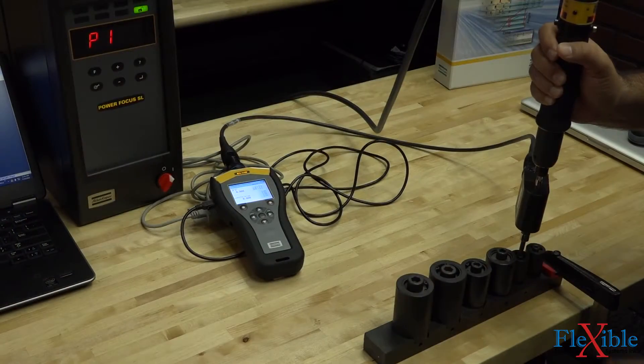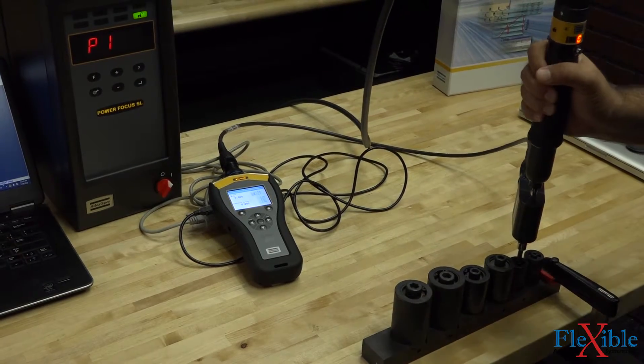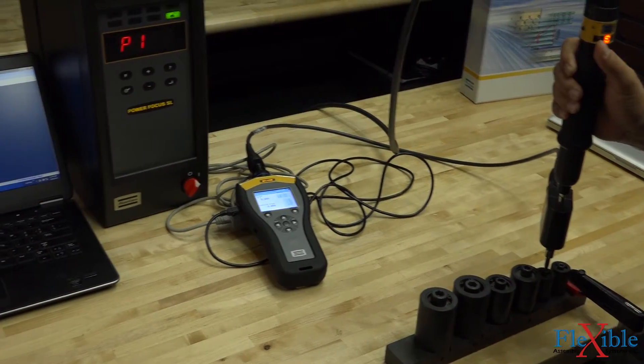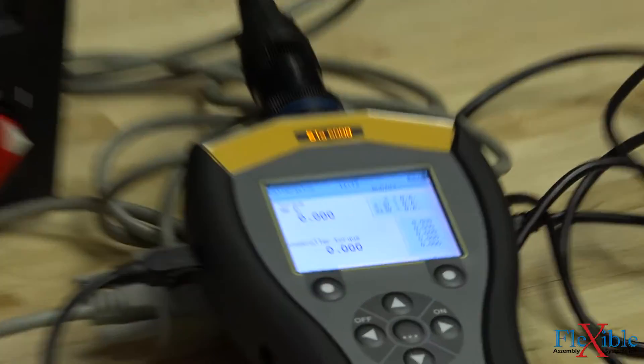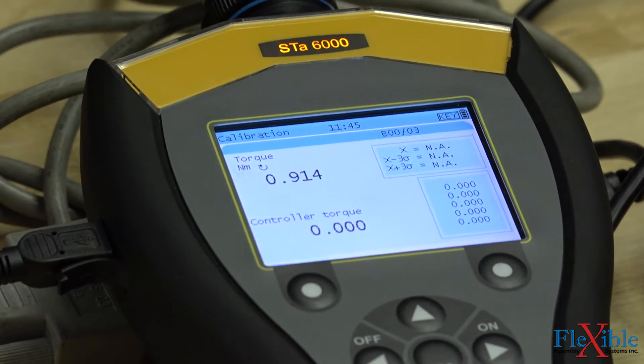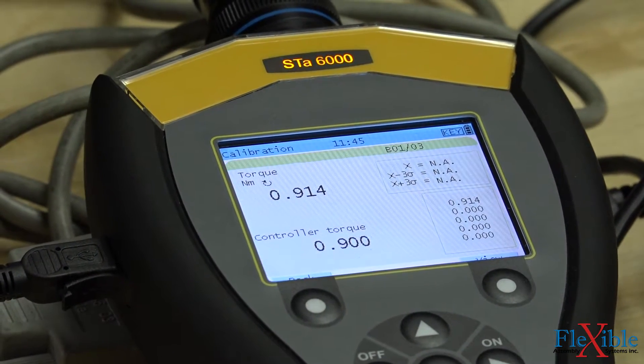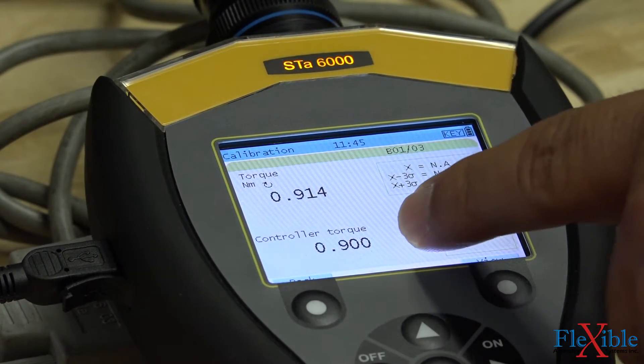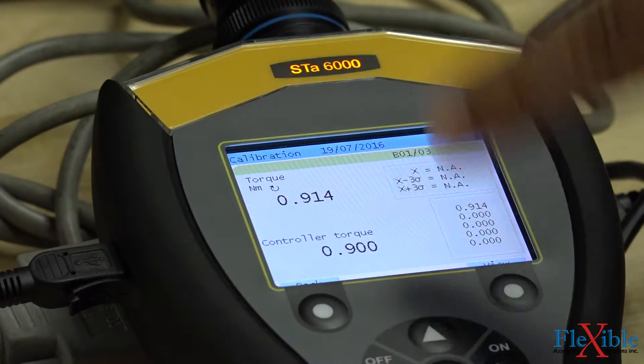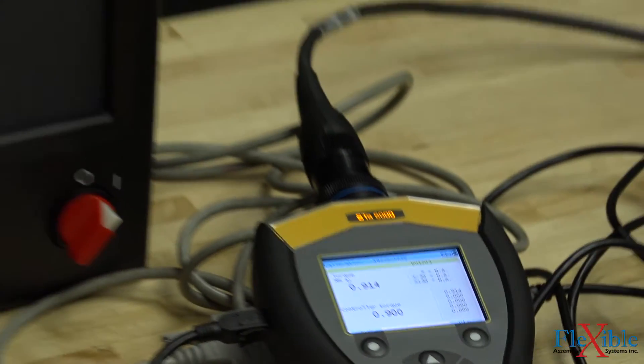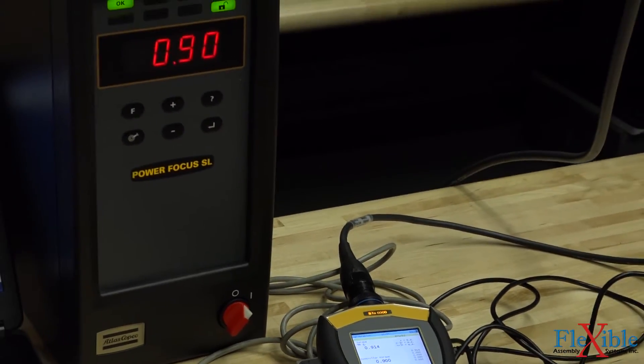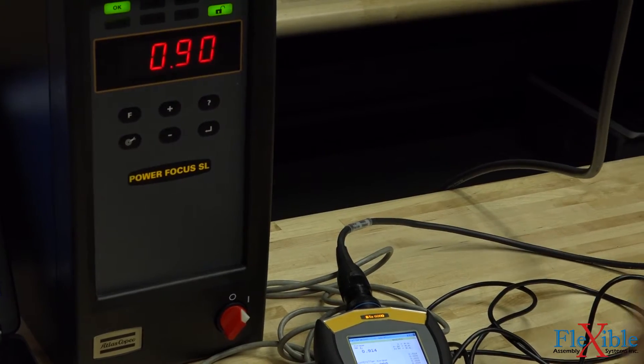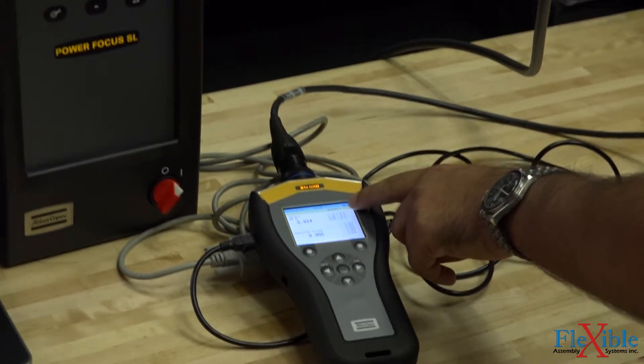We will now start our rundowns. After our first rundown, we see that the controller is displaying a value of 0.9 Nm, while our transducer measured 0.914. The batch count shows we have performed 1 readings out of 3.